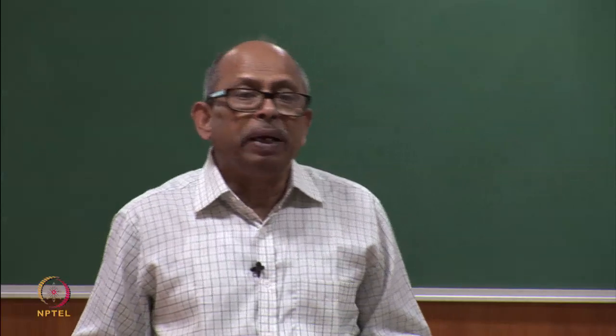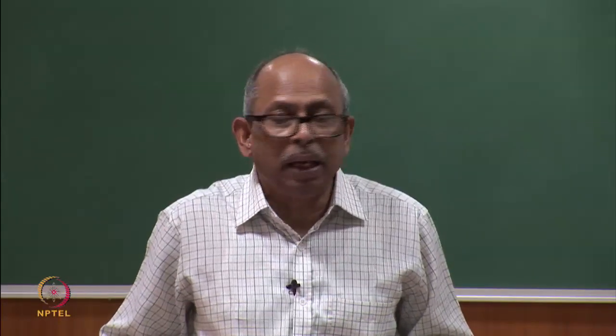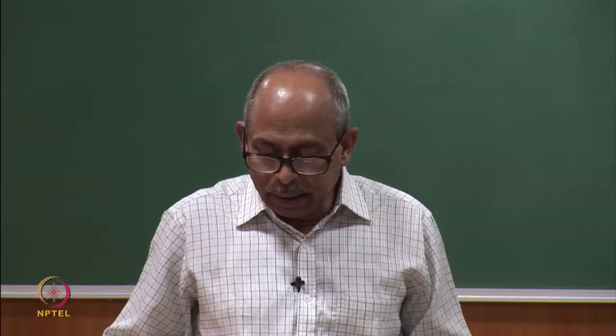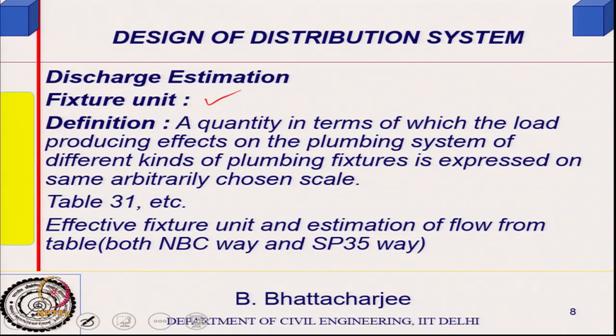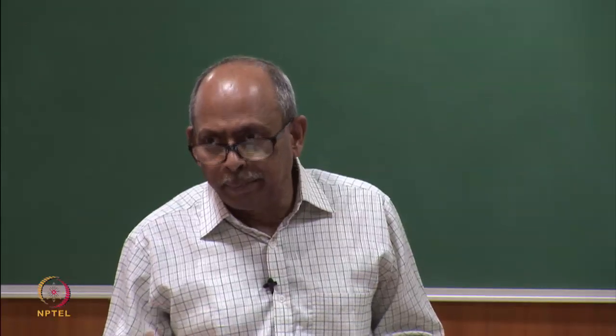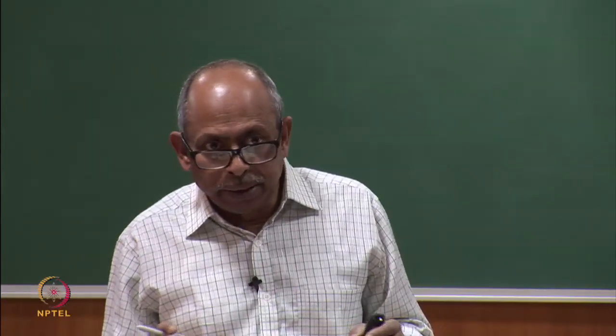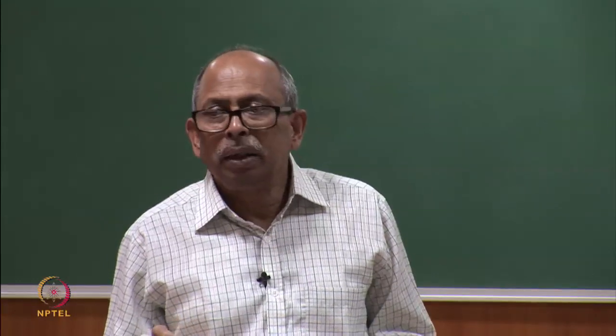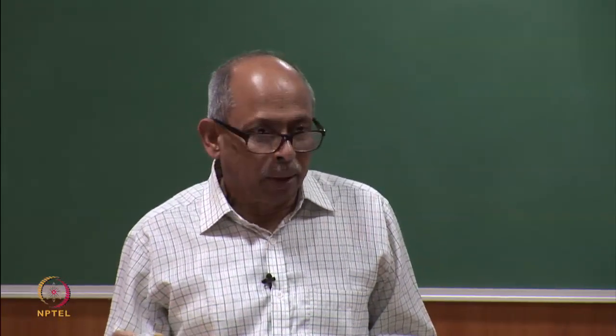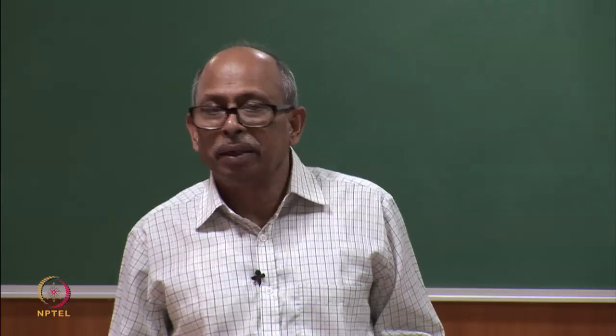Generally, I would like to find out the supply rate or quantity of supply required. This is arrived at using something called a fixture unit. If you look at the appliances you use — for example, a tap or a shower — they do not all require the same flow. A tap requires much less flow compared to a shower, so flows from different discharge outlets are different.